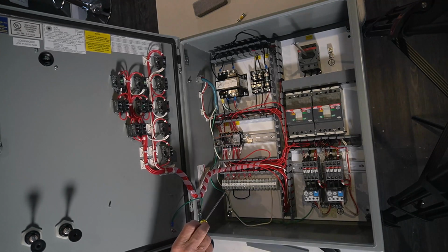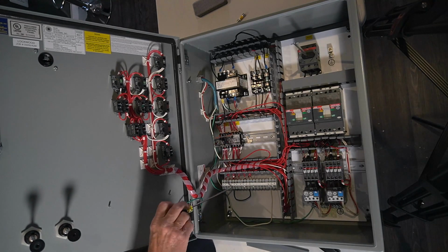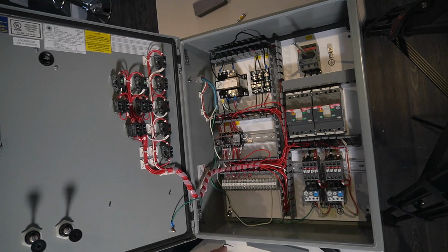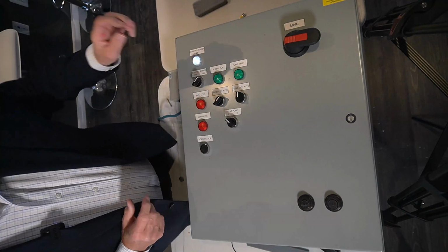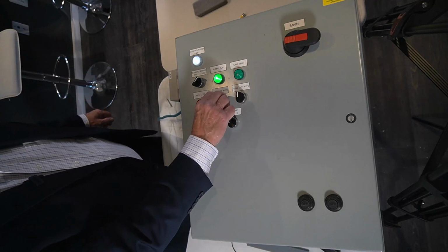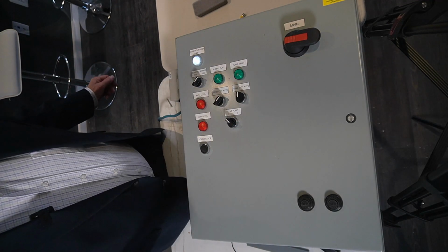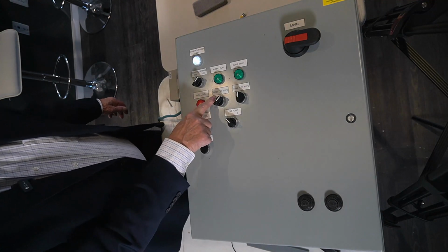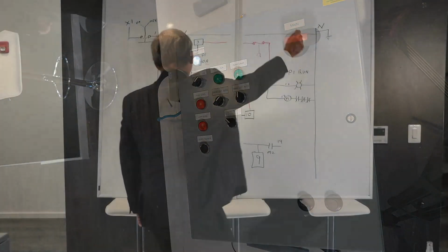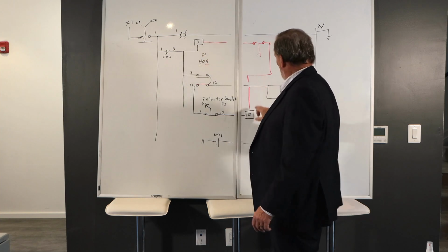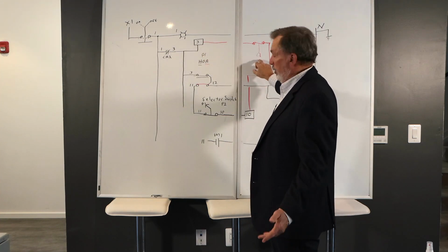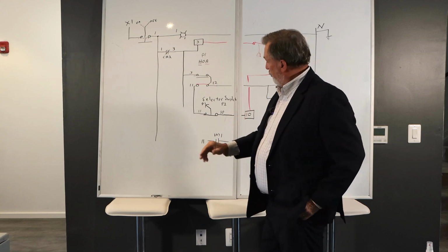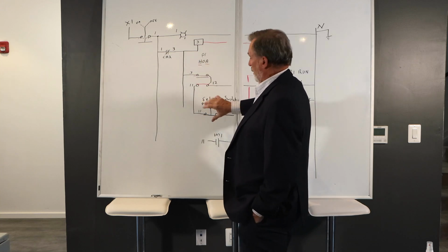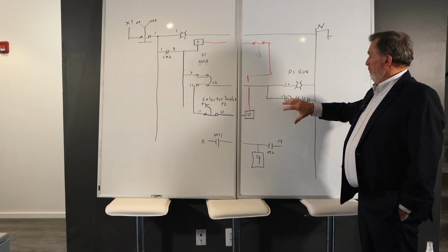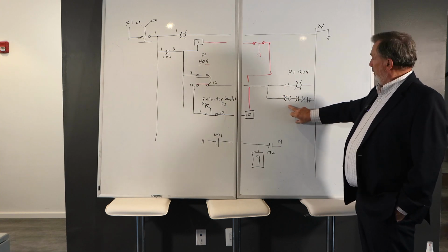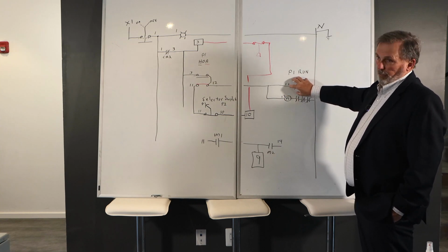I'm going to disconnect this jumper. Same situation, pump 1 works in hand, does not work in auto. For the pump to work in auto, I have to make 3 has to make 10 through the switch, which I simulated with the jumper. So what we have is an HOA, we have a pump selector switch, we have a motor starter for pump number 1, and we have a motor starter pump run light.